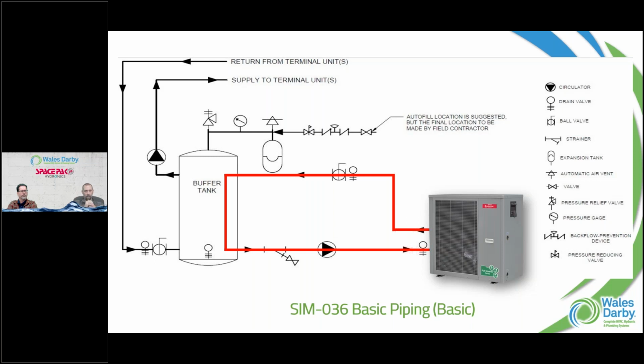And then the rest are kind of accessories that we would recommend, strainers, maybe a magnet separator, who knows, then on the other side of that tank. But there's some things you definitely would want to have on there, isolation. We've got to talk about insulation as well. It's always, heating wise might not be a big deal to you, but chilled water now, we're moving 47-degree water in the summer with 80% humidity out there, that pipe's going to be sweating like crazy. So insulation is key, you can never have too much on a chilled water system.